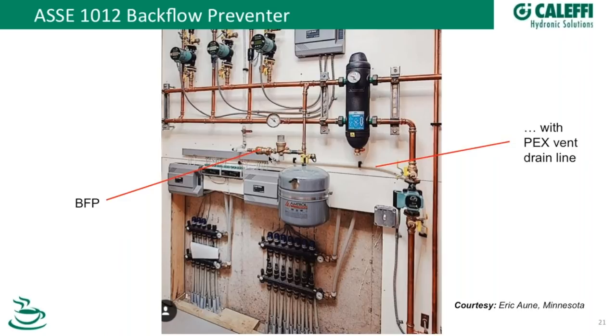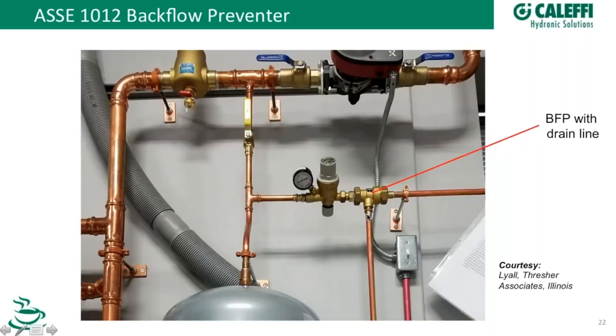This slide nicely illustrates containment and isolation again. They're containing the building on the supply side with a vertical double check, so nothing goes back into the city mains. Then they're isolating fire protection with a second double check, keeping their water safe from the fire protection system. The 1015 shown there is a low hazard backflow preventer, likely going to fire protection with no chemicals, but needing a backflow preventer because of the materials used in that fire protection system.